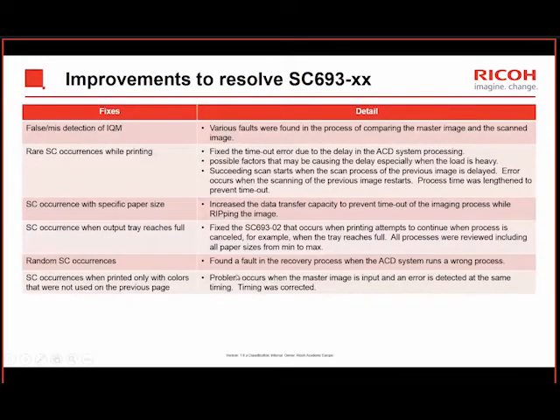Okay, some of the improvements: we had some misdetection before, and various faults when comparing the master image with the scanned image, and they've rectified those. There was also a timeout error with the ACD which they've rectified, and they've increased the data transfer capacity to prevent timeout errors. So they've done a lot of firmware fixes to make this unit work.